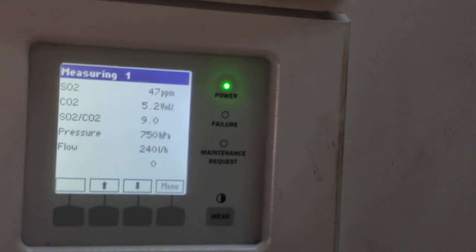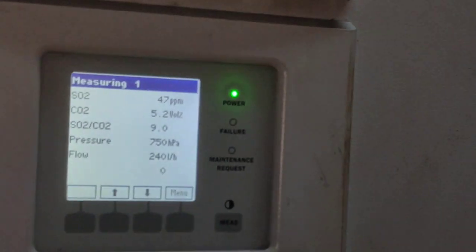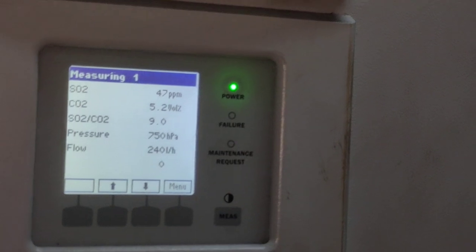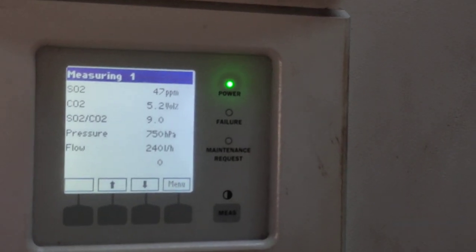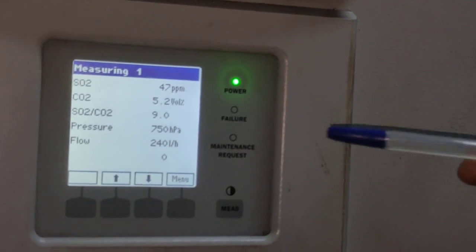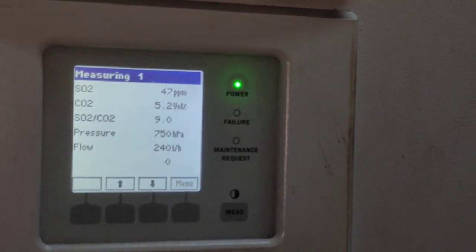So during this 16 minutes time the alarm will stay every day. Actually this alarm is not supposed to come. The same was discussed with the technician also, and the technician advised us, if we need to have this daily zero calibration, you can have, otherwise you can inactivate it.